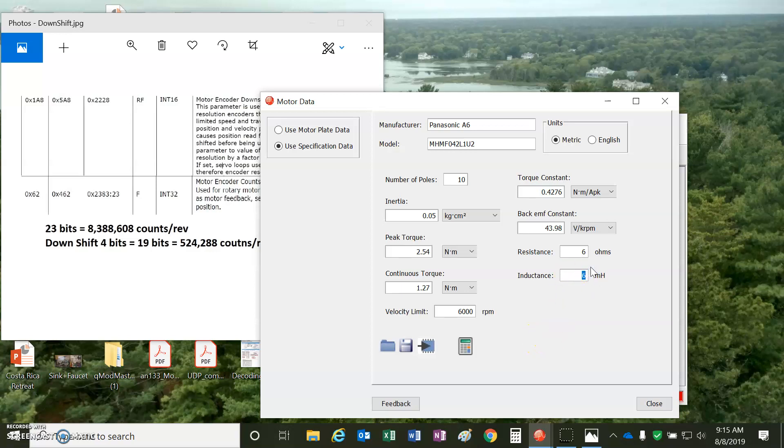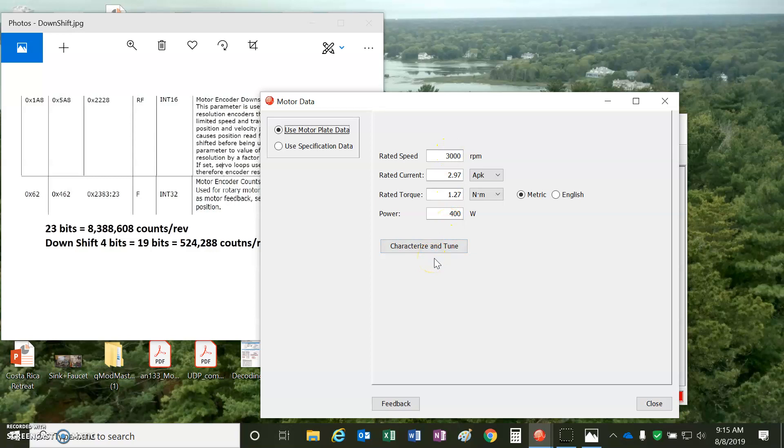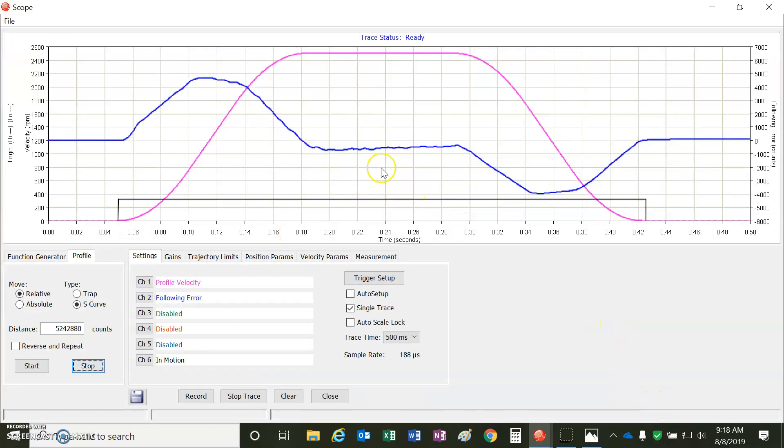And I just gave a guess for the inductance. And 6,000 RPM, this thing can go that fast. That's not the rated speed. But for short durations, I'm sure the watts coming out of the motor will be fine with that, if you have sufficient bus voltage to do that. The alternative is to use the ratings label and just enter the data and use the characterize and tune. If you don't have all the spec-y data, you can run through this auto-tuning thing. But you have to downshift the encoder first before you do that, because otherwise the speeds will be too slow.